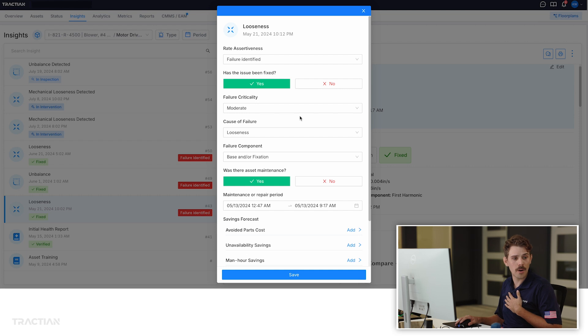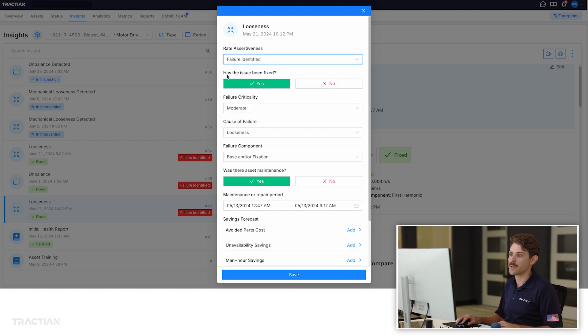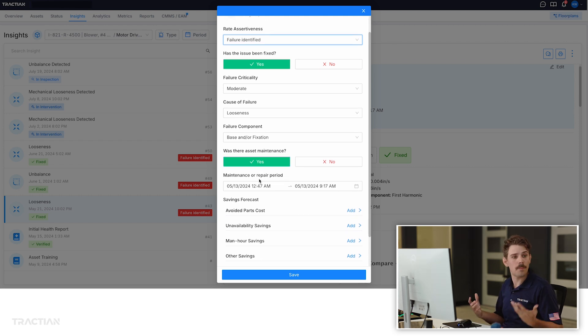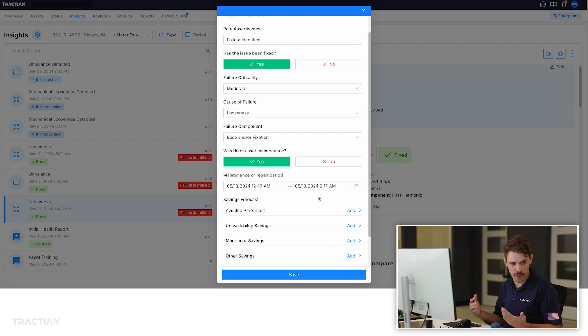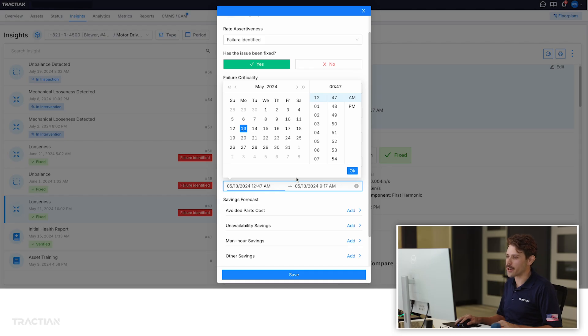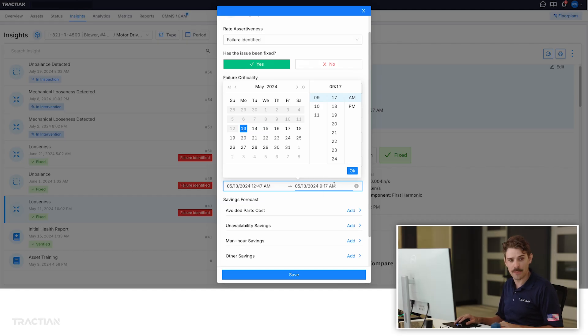Marking it fixed means we've identified a problem, corrected it, and are now taking steps to quantify it. We confirm: was a failure identified — yes; has the issue been fixed — yes; was there asset maintenance — yes, we put a bolt back and secured that motor to its base. That happened on the 13th from around midnight to around 9 in the morning — the night shift took care of it. We need to understand the maintenance time window because we want to ignore any data during that period. We're not trying to alert on maintenance activity; any data after that end date becomes part of the new health baseline, and we retrain our sensor accordingly.